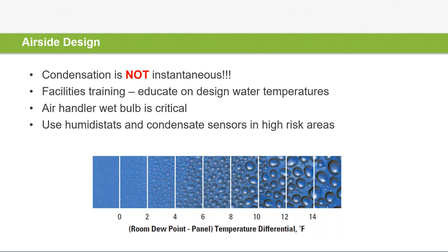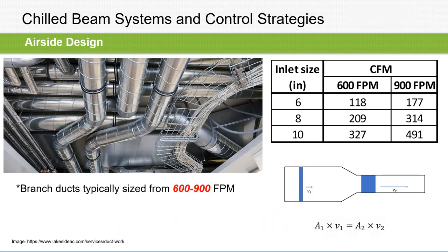You can bring the water temperature up, or you can recirculate and stop sending water to that zone if it's at risk. So there's a few ways to do it, but it essentially becomes a control issue and not so much a chilled beam problem. But we don't see this very often, and I think it's usually because people do a good job designing systems and put the right safeties in place. So people have been successful with this and do not actually see condensation very often.